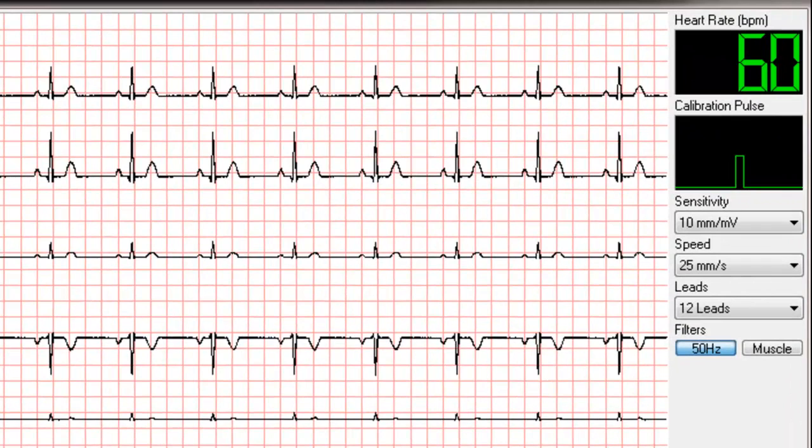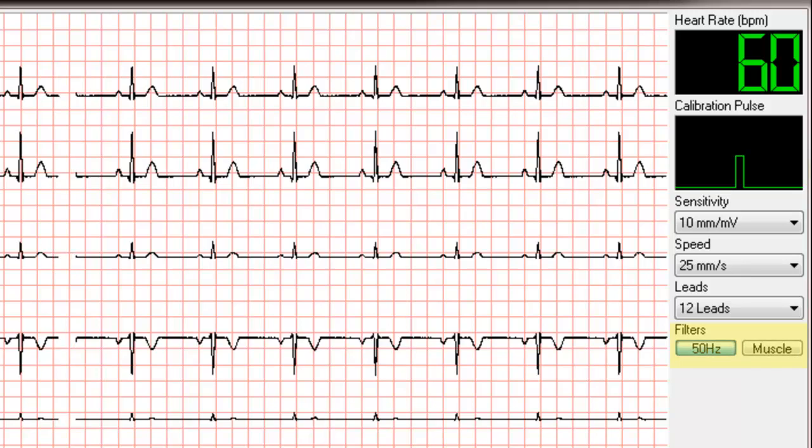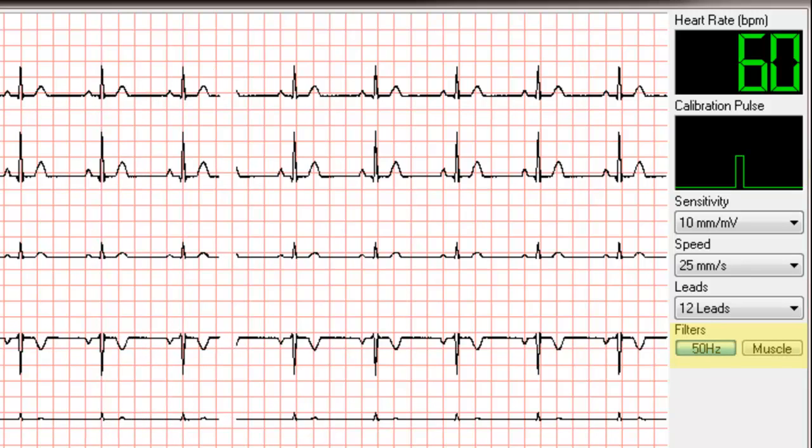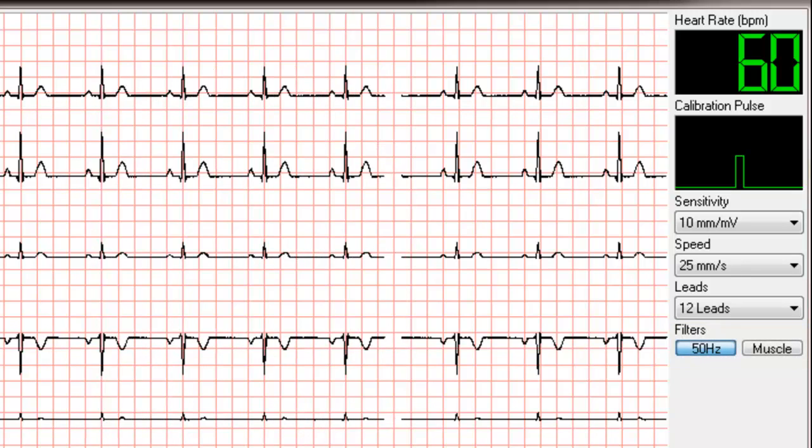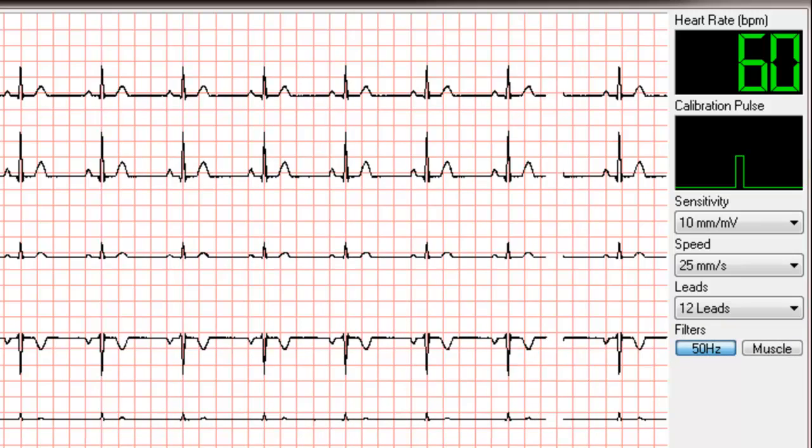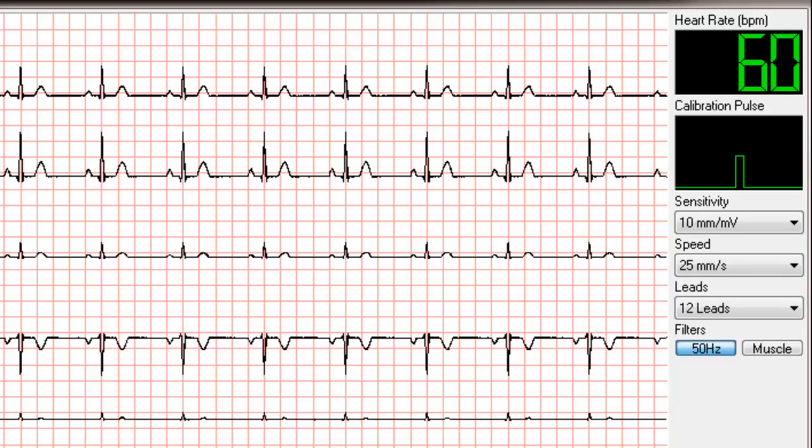The Universal ECG system has two filters. The 50 Hz power filter will reduce noise or fuzziness appearing in the trace caused by interference from other electrical devices. This filter should be defaulted to ON. Dependent on your operating system, the button will either be depressed or shaded blue to indicate the filter is active.